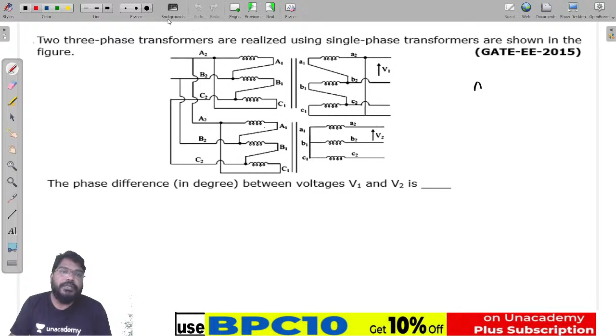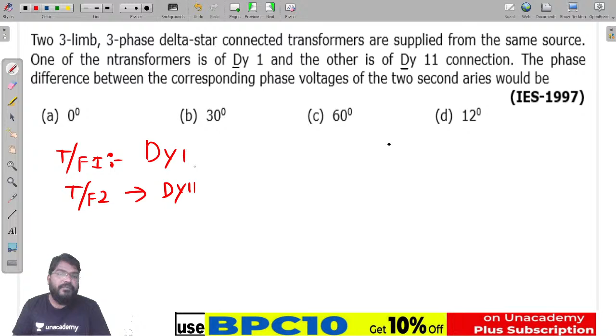So it is the same question. Here in the two 3-limb three-phase delta-star connected transformer supplied from the same source, transformer 1 is a DY1 and transformer 2 is a DY11. The phase difference for DY1 is minus 30 degrees, that is 30 degree lagging, and DY11 is plus 30 degrees. Now what about the phase difference between these two transformers? It is equal to plus 30 degrees minus of minus 30 degrees, so it is equal to 60 degrees.